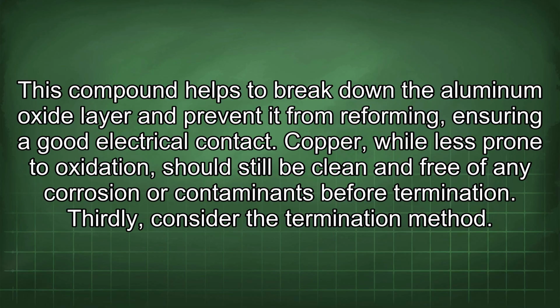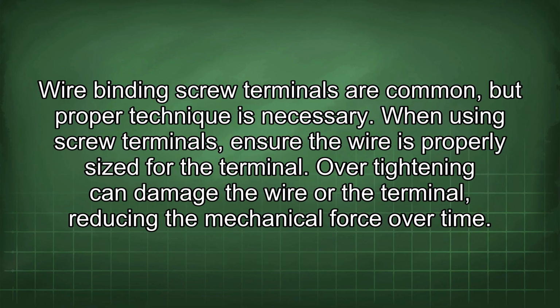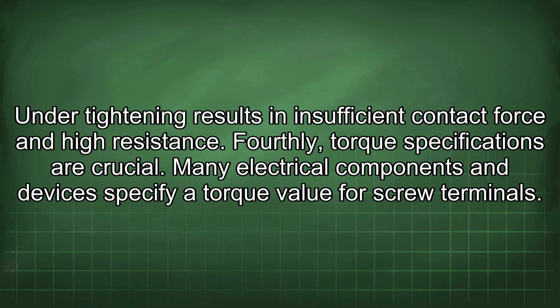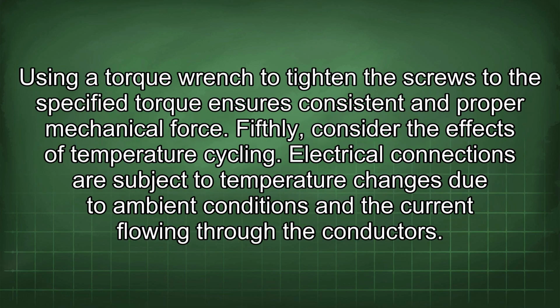Thirdly, consider the termination method. Wire binding screw terminals are common, but proper technique is necessary. When using screw terminals, ensure the wire is properly sized for the terminal. Over-tightening can damage the wire or the terminal, reducing the mechanical force over time. Under-tightening results in insufficient contact force and higher resistance. Fourthly, torque specifications are crucial. Many electrical components and devices specify a torque value for screw terminals. Using a torque wrench to tighten the screws to the specified torque ensures consistent and proper mechanical force.